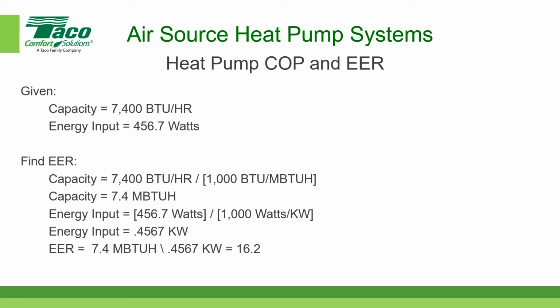So, if you want to find out what the COP is, divide 16.2 by 3.412. So let's do it. 16.2 divided by 3.412, and the COP is 4.7. So COP can be converted into EER and vice versa, but only in America do we use this silly thing called energy efficiency ratio. It's just a different way of saying the same thing.